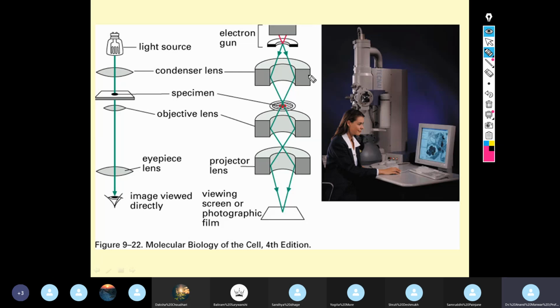For example, if you talk about the condenser lens, the magnetic condenser lens, its function is that it focuses a parallel beam of electrons on the specimen. Whatever beam of electrons is coming from the electron gun, with the help of this magnetic condenser lens, it will focus this beam of electrons on the specimen sample, right? Then the second lens in the central column is the magnetic objective lens. What is the function of the magnetic objective lens? Its function is to form a real and magnified image.